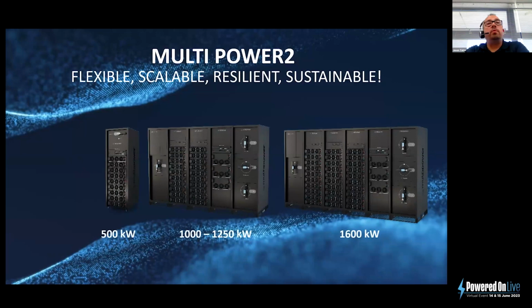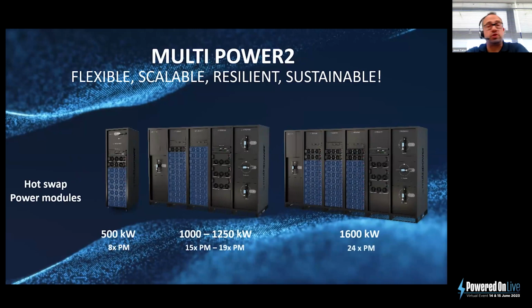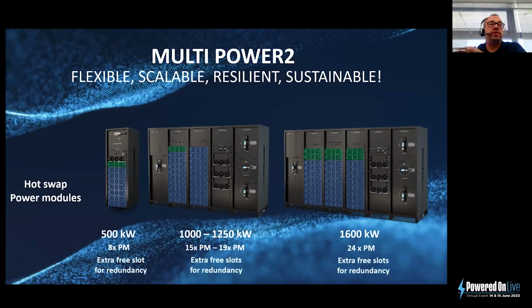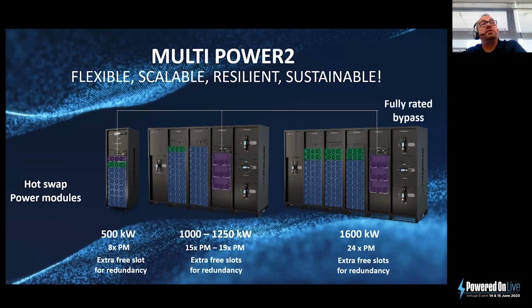Now, within all of these cabinets, as I was saying, the module forms the core of the cabinet. So basically, the systems are populated with fully hot swappable power modules to suit the load required at the time. In addition, inside those cabinets, you've got spare slots where you can fit redundant modules, so you can have redundancy levels. In addition to this, the system has a fully rated bypass cabinet.